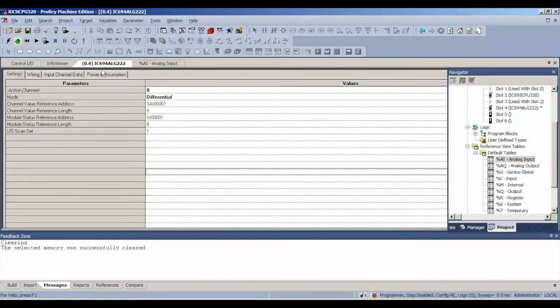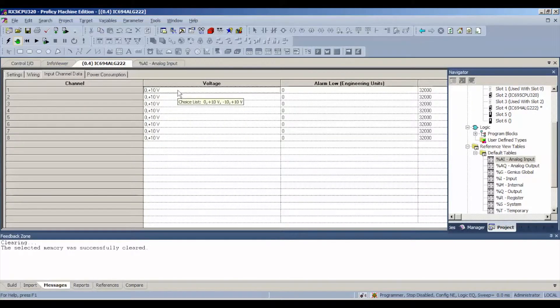The eight channel differential mode has the ability to do negative or positive 10 volts DC. One easy way to do negative 10 volts DC is obviously just to switch your polarities on the power source you're using. In other words, making your common, which is terminal screw number 19, your positive lead rather than your negative lead. I hope that makes sense. That's pretty much the entire test.